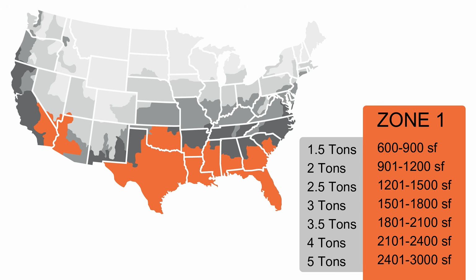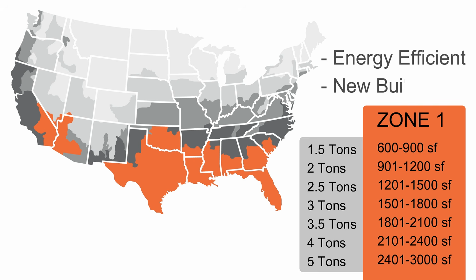So you might be asking, well, why is it also recommending that I can put a 3-ton on an 1,800 square foot home? Well, the short answer is that's probably a newer home, and newer homes can get away with that just due to a lot better insulation, double pane windows. It could be sealed a lot better. So typically, what we see is homes that call for a smaller system with a larger square footage is going to be a more energy efficient home, or even just a newer house in general.